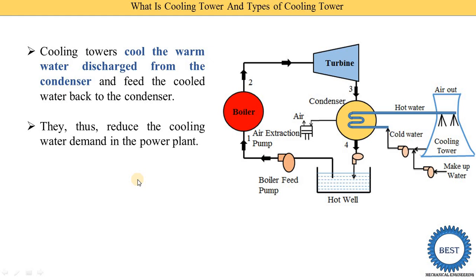Suppose a thermal power plant is near a river where water is available in a large quantity. In that case, we can use continuous fresh water from the river, supply it to the condensers, and the hot water is directly discharged back into the river. But when the quantity of water is limited, we need to use the cooling tower — meaning we can reuse the same water again and again, reducing the overall water requirement.